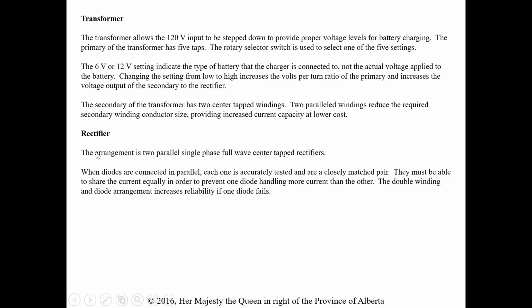Okay, the rectifier section, again, the arrangement is two parallel single-phase center tap rectifiers. When diodes are connected in parallel, each one is accurately tested and closely matched, because they have to share that current equally. If they're not, one will take more and potentially damage the diode. The double winding diode arrangement increases reliability if one fails too.